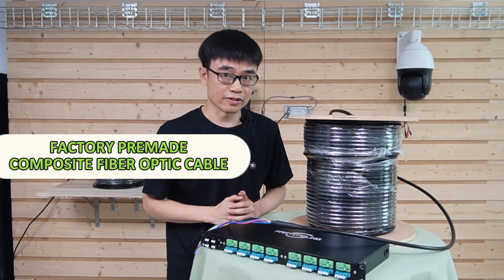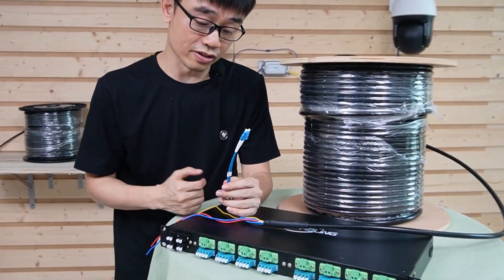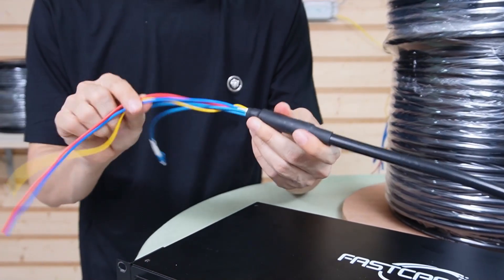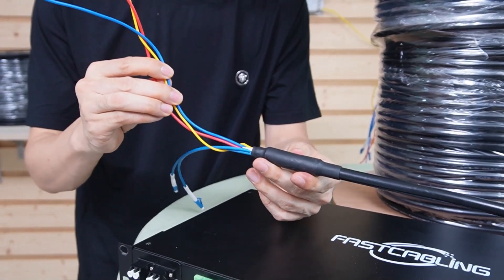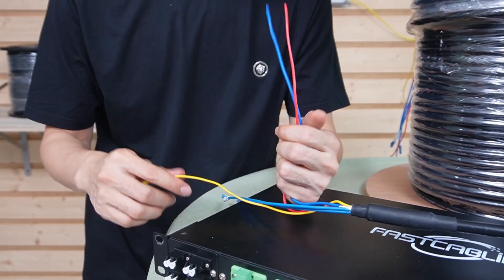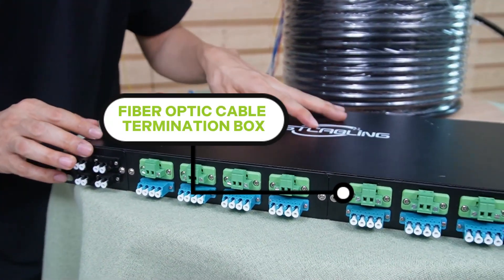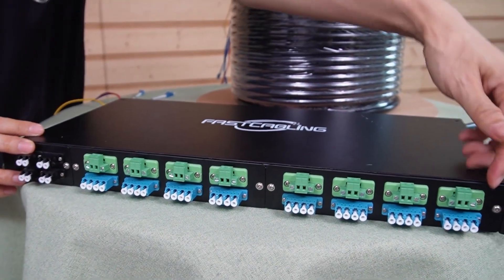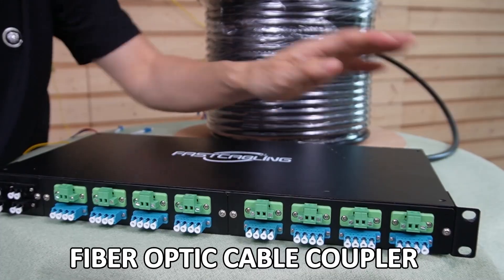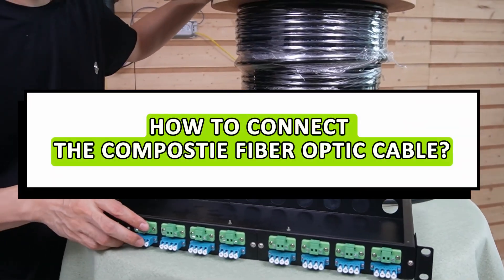This is the factory pre-made composite fiber optic cable. The connector is made in the factory with a pulling eye. I need to remove the pulling eye — with it, we can pull the cable through the conduit directly. Three copper wires are integrated into this fiber optic cable. We will take two copper wires to send the low voltage power from the control room to the camera, and we have one grounding wire.